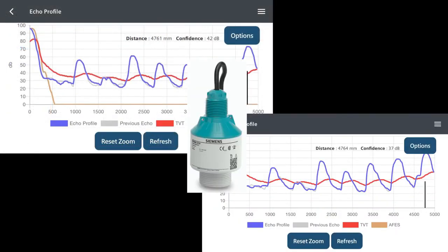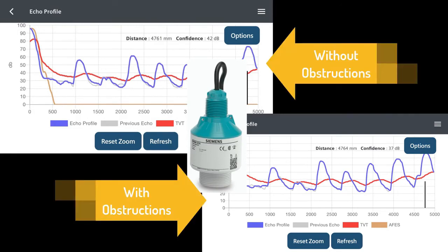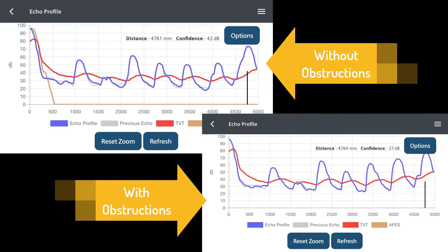So now we'll have a look at the radar, the SITRANS LR110, and this device is performing extremely well with all these obstacles. In fact, there's only one of the obstacles out of all of them that's creating a larger echo, and that's the aluminium steps.